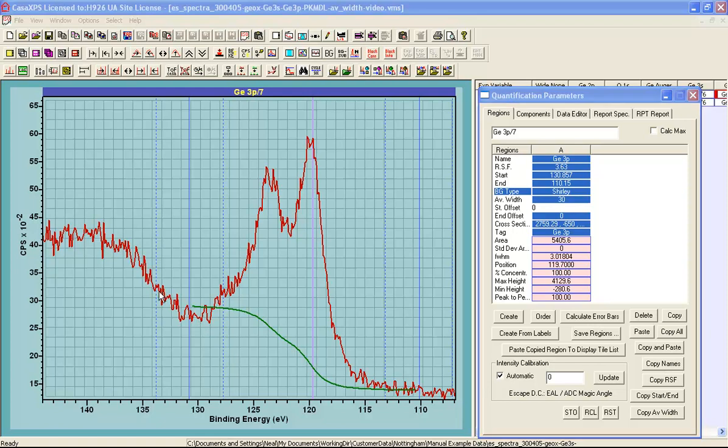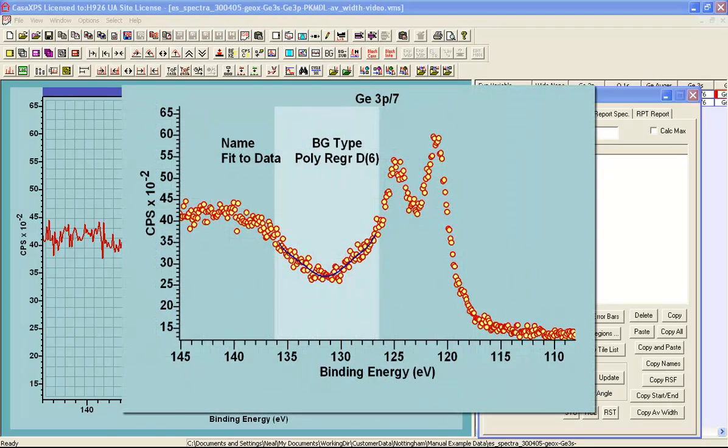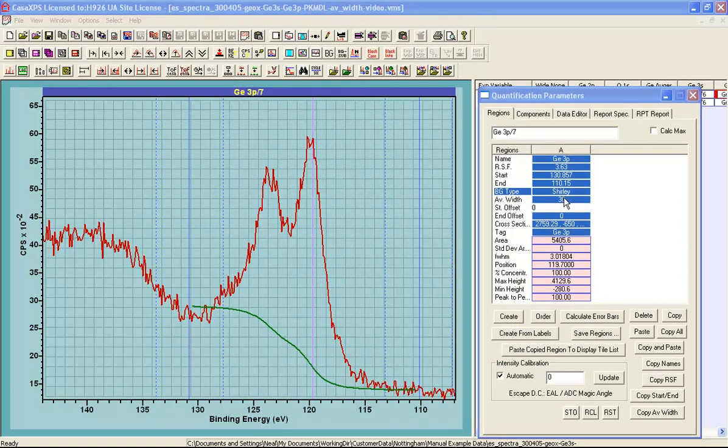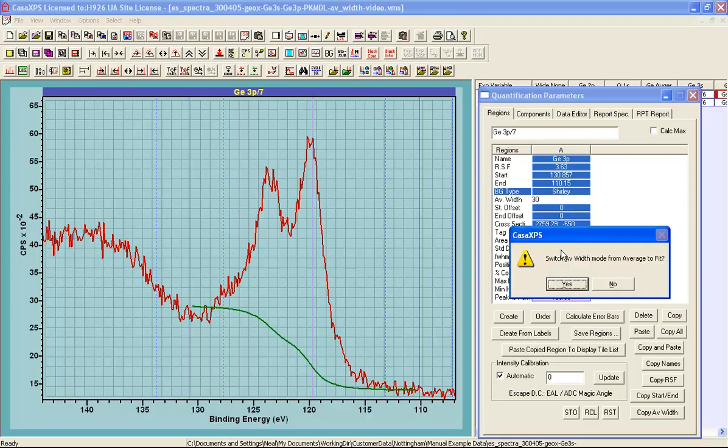The alternative to a straight average is to calculate a polynomial that fits the data within this interval specified by the average width. We can switch to this alternative mode by pointing at the field before it is an edit field. So I cannot edit the 30 by entering a new number at this point. I would have to click here in order to turn it into an edit field. So in this state I hold the control key down and click. Then an option is given to me whether I want to switch between the average mode or to fit these data. When I say fit, this means fitting a polynomial to these data based on the interval specified by the average width.